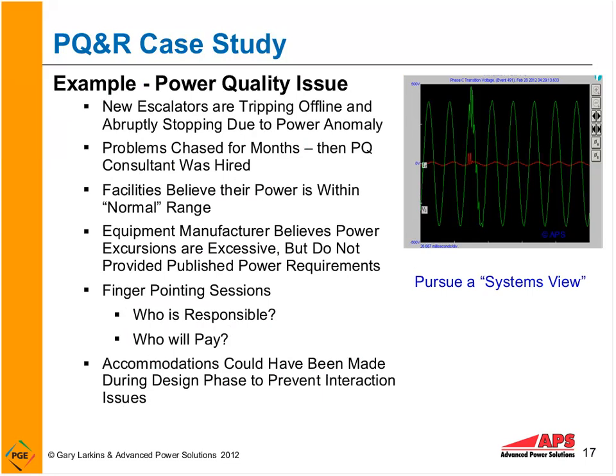So the problems were chased for months. The contractors and the equipment vendors chased them for months. They suspected power quality issues, but they couldn't pin them down. The power quality monitors, or analyzers as they called them, that they were using were not capable of seeing the disturbances that were causing the shutdowns. I was brought in to look at the situation.